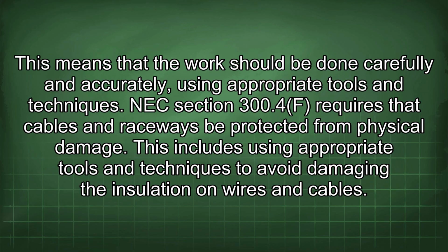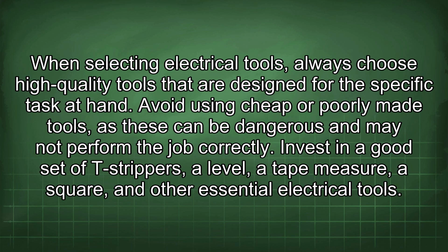NEC Section 300.4(F) requires that cables and raceways be protected from physical damage. This includes using appropriate tools and techniques to avoid damaging the insulation on wires and cables. When selecting electrical tools, always choose high-quality tools that are designed for the specific task at hand. Avoid using cheap or poorly made tools, as these can be dangerous and may not perform the job correctly.